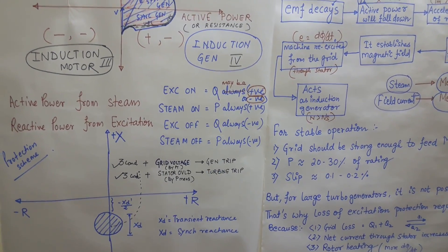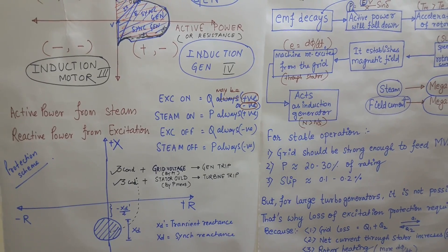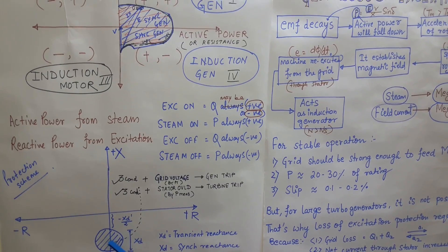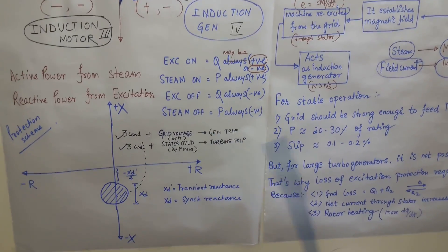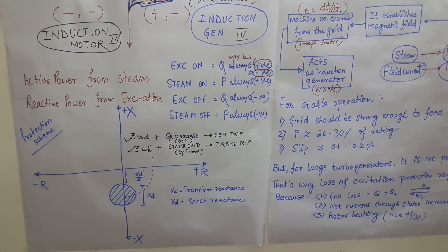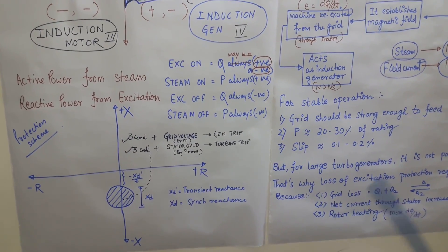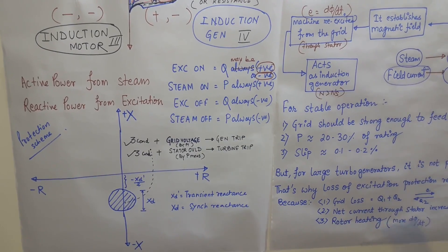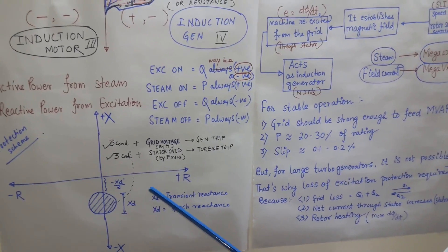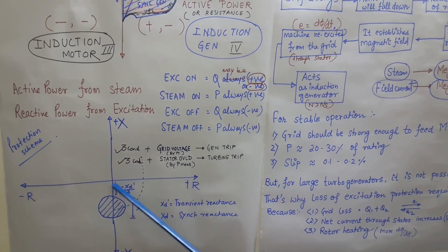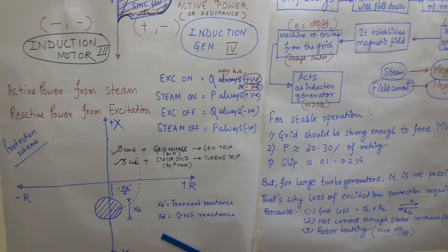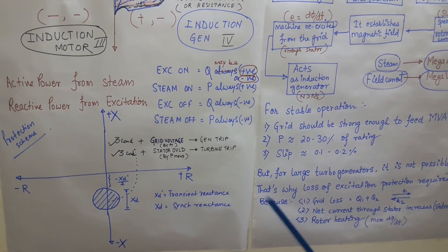For loss of excitation protection there are certain conditions which are compulsory. Condition 1: the operating point has to enter into the locus for a certain time period. Condition 2: the rotor winding should experience under voltage. Condition 3: the reverse reactive power — meaning the reactive power drawn by the generator — has to be more than a certain limit.